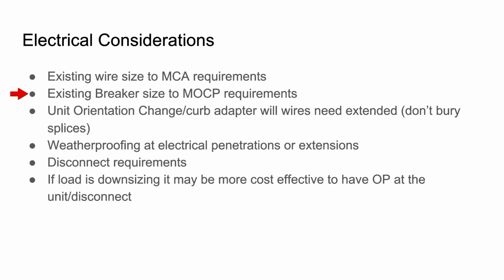And then the existing breaker size on a unit, that's going to be what they call MOCP, maximum overcurrent protection, or sometimes it'll list max fuse size. And so that's saying what is the biggest breaker you can have on this.